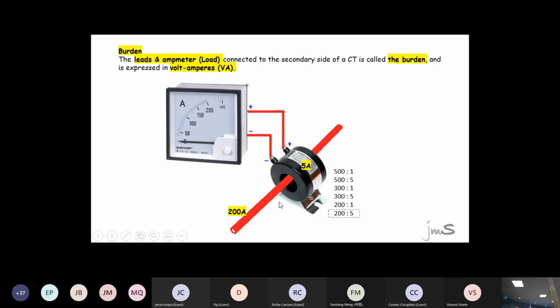Now look what's going to happen. If 200 amps flows in the bus bar, the magnetic field cuts through here. What is the maximum amps which will flow in the winding and in these wires? Look there, 5 amps, 5 in, 5 out. Got it? But what will the amp meter say? 200 amps.